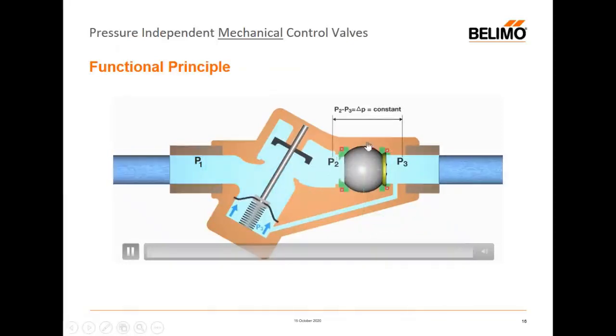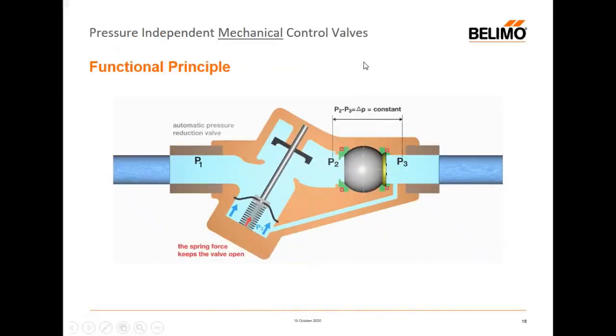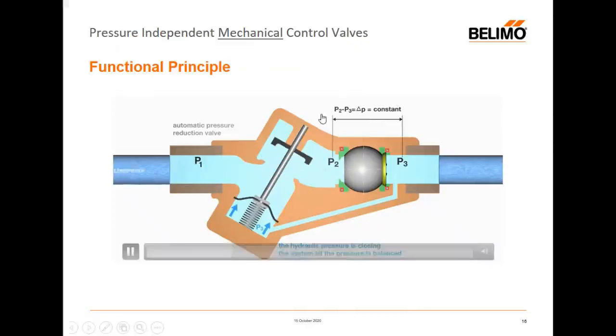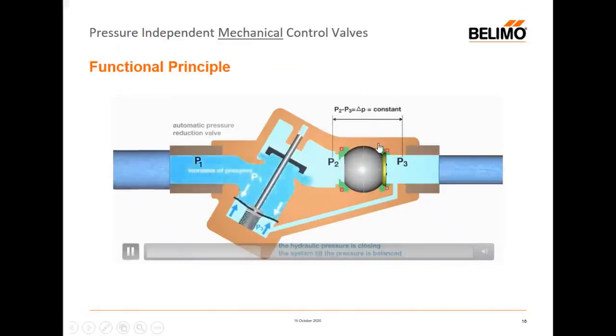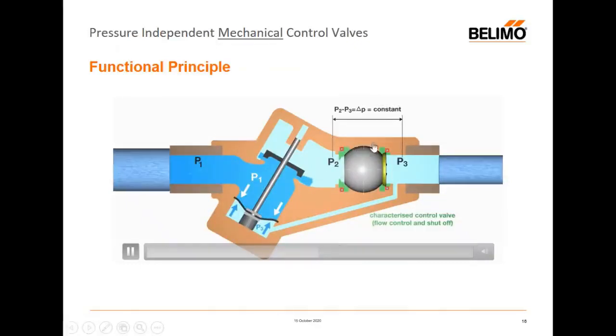So by maintaining a constant differential pressure at all times, varying perhaps the KV with the actuator, which will move the valve open and close, so the KV might change, but we do know that if we know the available pressure and we know the delta P, which is a result of the KV, we will know the flow.